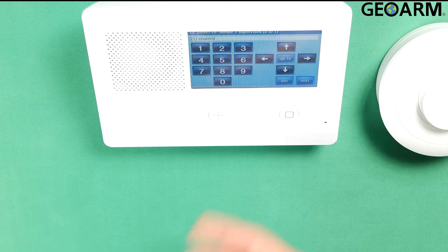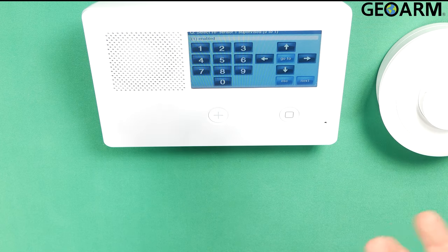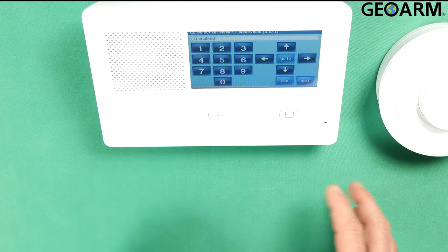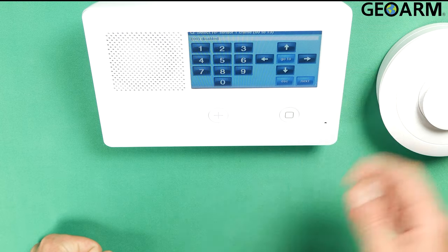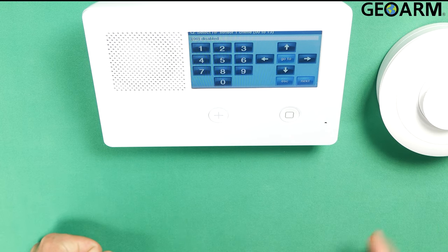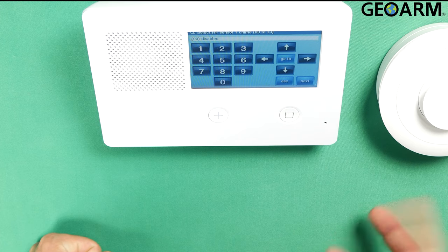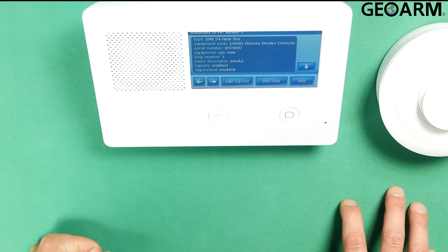Now it wants to know if this device is supervised, meaning that it's checking in with the panel to let it know it's all right. It's got a good battery. It's not falling out of RF supervision. It's not being interfered with. I'm going to leave that because I do want that to happen. So press the down arrow. Now it wants to know if you want to chime this. This is a smoke detector so these devices typically don't chime. So I'm just going to skip that. Press the down arrow.